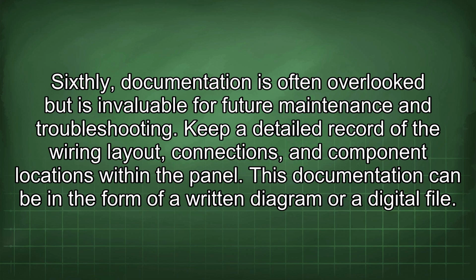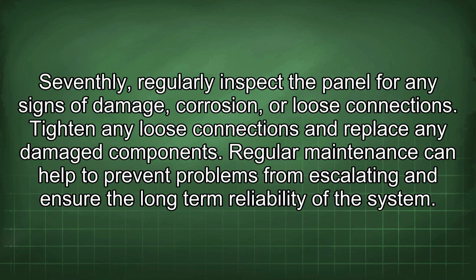Sixthly, documentation is often overlooked but is invaluable for future maintenance and troubleshooting. Keep a detailed record of the wiring layout, connections, and component locations within the panel. This documentation can be in the form of a written diagram or a digital file. Seventhly, regularly inspect the panel for any signs of damage, corrosion, or loose connections. Tighten any loose connections and replace any damaged components. Regular maintenance can help to prevent problems from escalating and ensure the long-term reliability of the system.